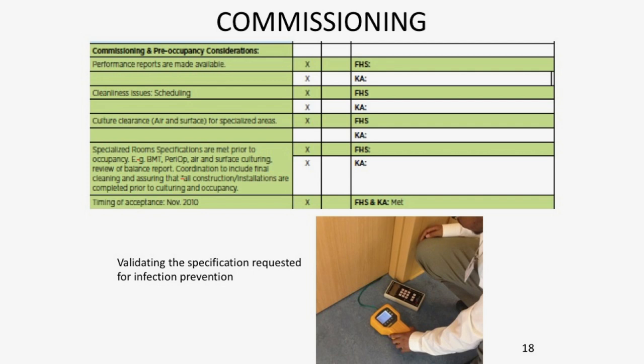If you got what you paid for, you wouldn't be putting in this. What we have found in meetings that don't go well with vendors and contractors is the simple fact that the specification was never specified. If you say you want 2.5 pascals or a hundredth of an inch pressure differential, how do you know you got that? Who's going to tell you that? That's what performance-based specifications are really important for.